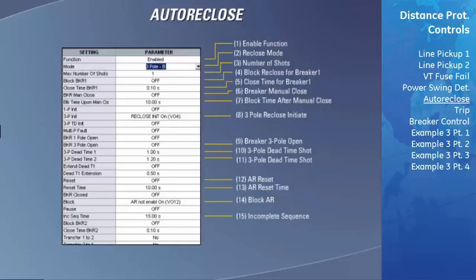The 3-pole dead time 2 field specifies the dead time for the second reclose attempt. In this case it won't be used since the maximum number of shots is selected as 1. The reset field indicates which input is used to reset the auto reclose if it is locked out. The auto reclose reset timer specifies the time from first auto reclose initiate until the auto reclose will be automatically reset after all or one shot reclosed successfully after the fault is cleared. The block field is used to block the operation of the entire auto reclose scheme. Here, virtual output 12 is the flex logic signal used to block the auto recloser.